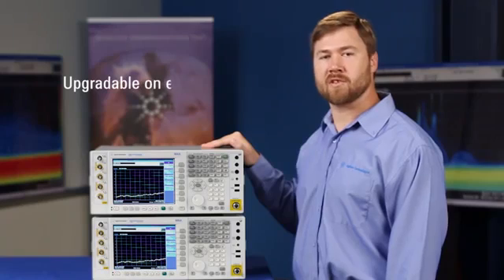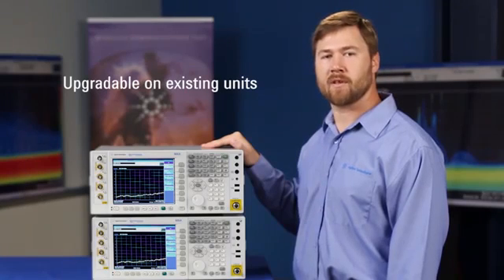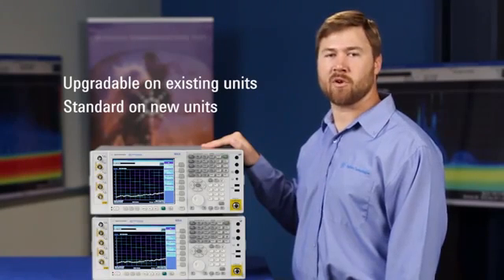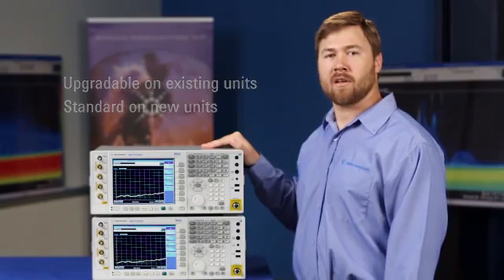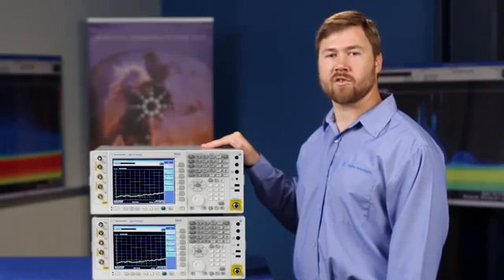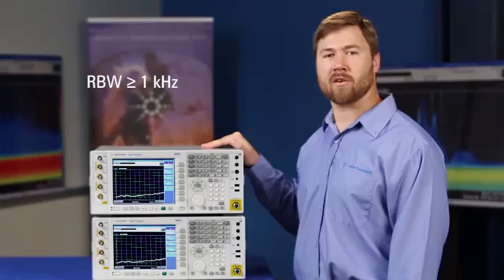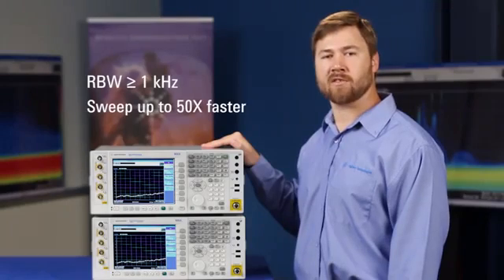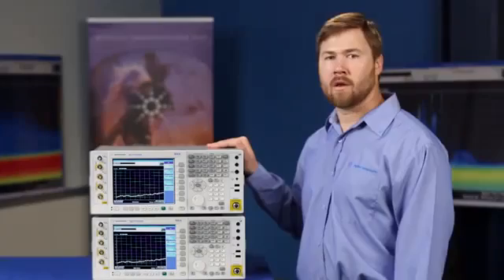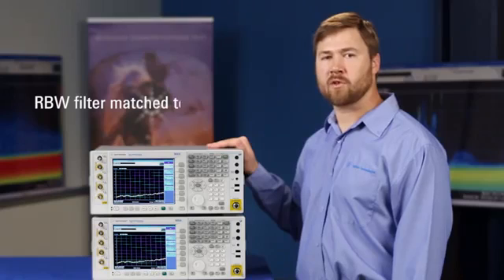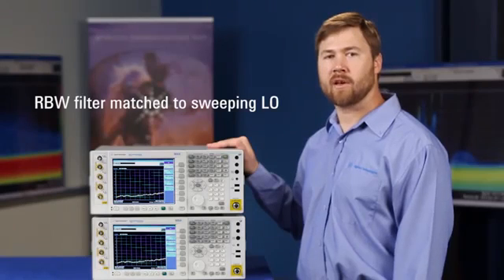These improvements come to existing customers with a firmware upgrade. They come standard to new customers with the purchase of an instrument. These sweep speed improvements work in resolution bandwidths of 1 kHz or greater and allow you to sweep up to 50 times faster than the previous generation. They work because we've implemented a resolution bandwidth filter in our digital IF that's matched to a sweeping local oscillator rather than a CW local oscillator as in the previous generation.